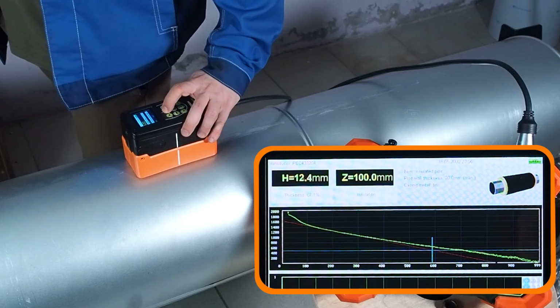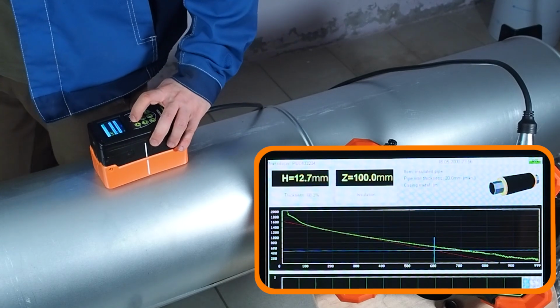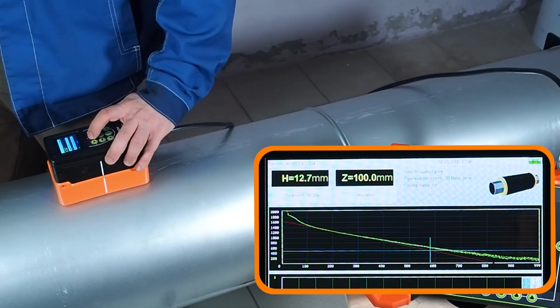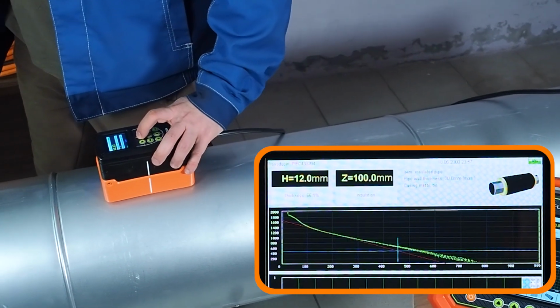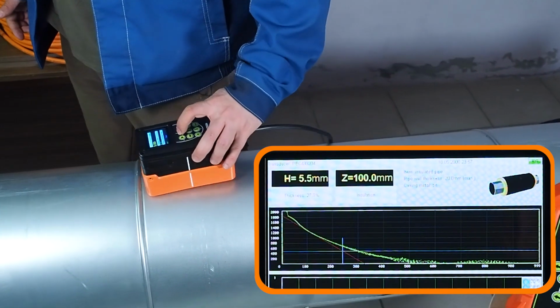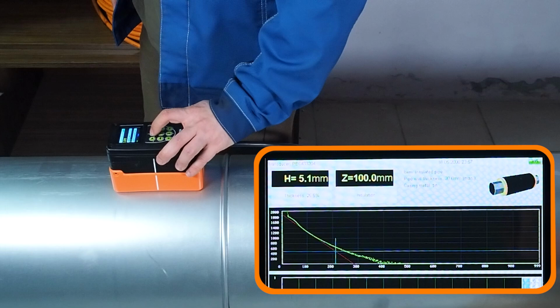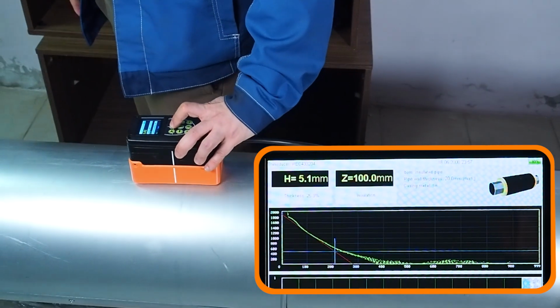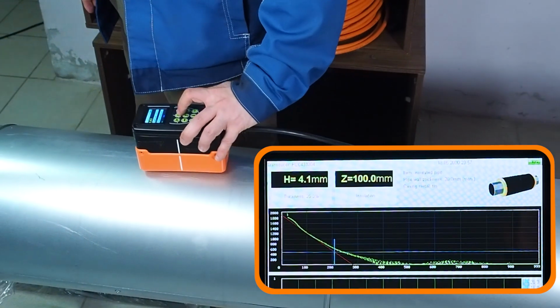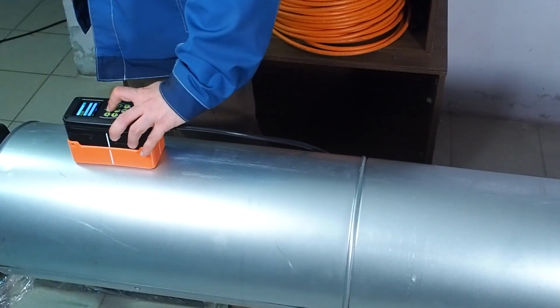We see that the device can measure the pipe wall thickness under both insulation and casing, including tin casings. Test results. The PE4332 pulse eddy current flaw detector has measured the pipe wall thickness under 100 mm thick insulation with both aluminum and tin casings.